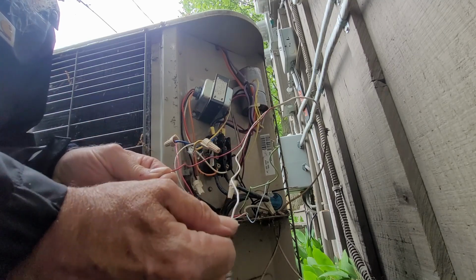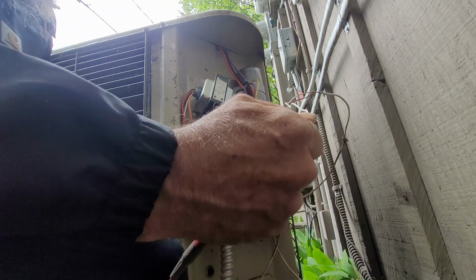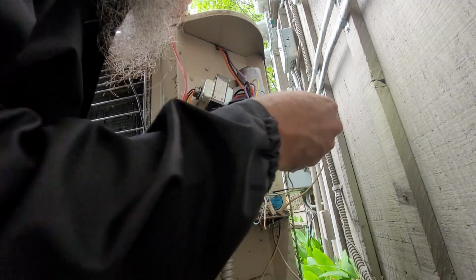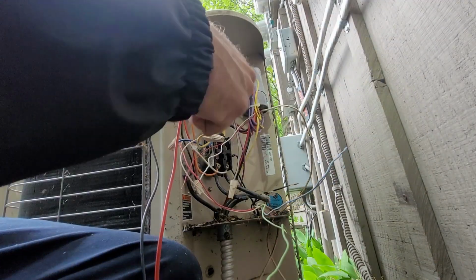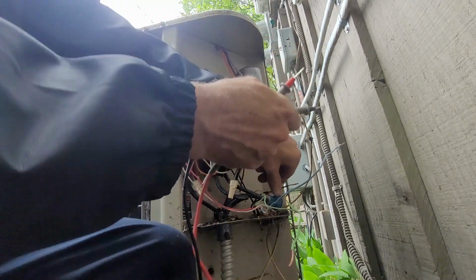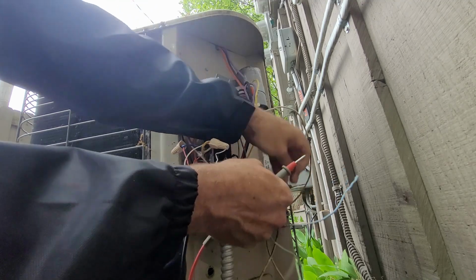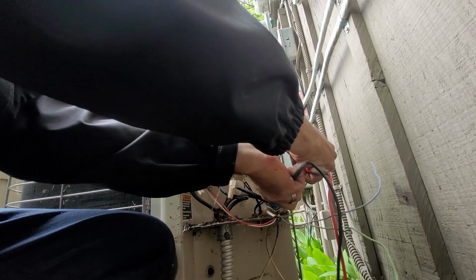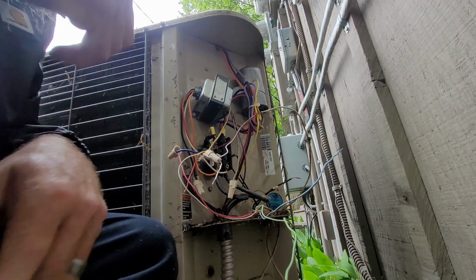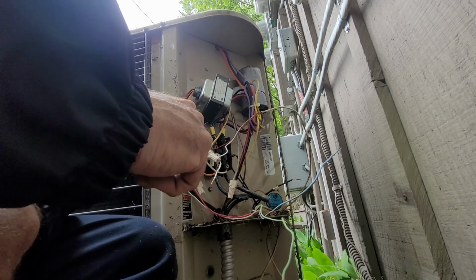I shouldn't have any. I don't. So I disconnect the interruptible, that's my switch leg for the interruptible. Technically, that coil should read 14 ohms. And it does.